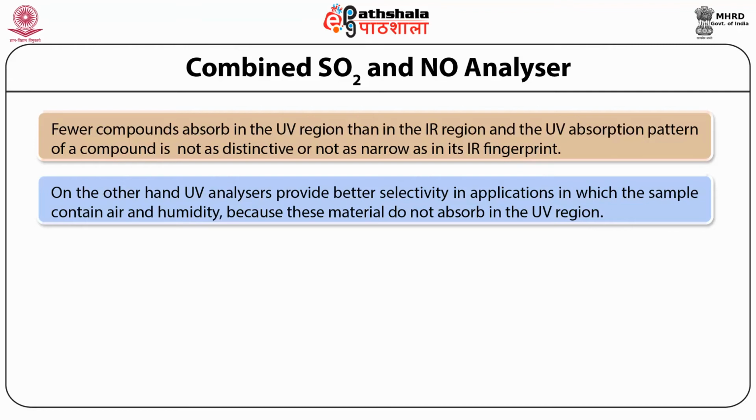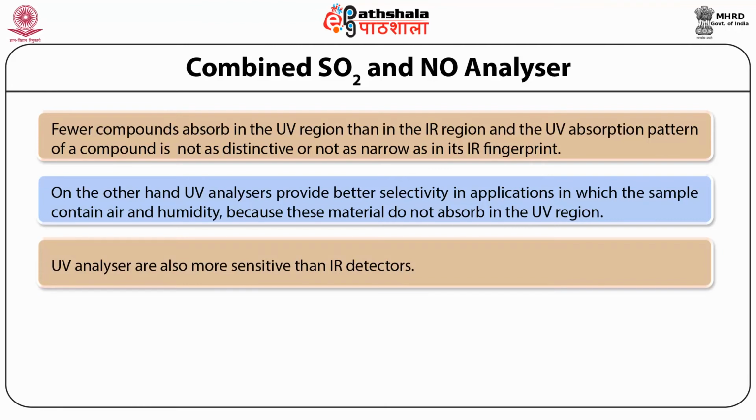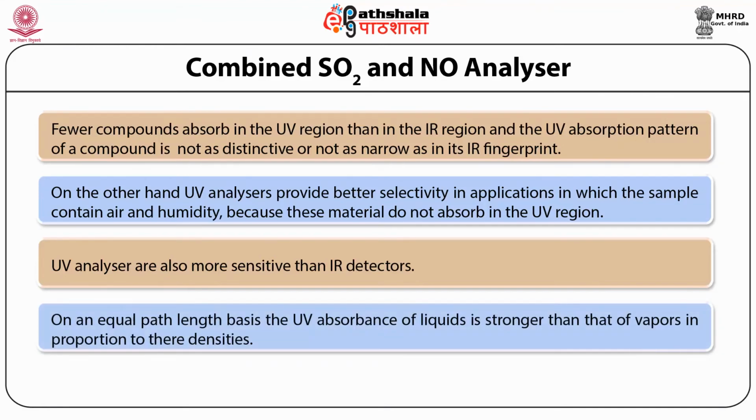because these materials do not absorb in the UV region. The UV analyzers are also more sensitive than IR detectors. On an equal path length basis, the UV absorbance of liquids is stronger than that of vapors in proportion to their densities.